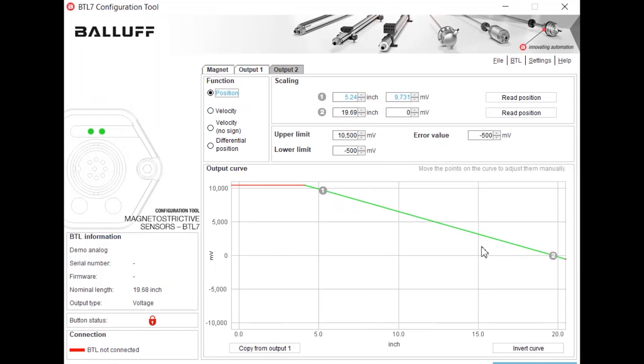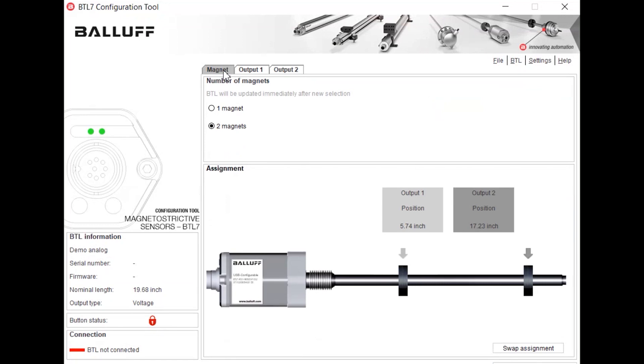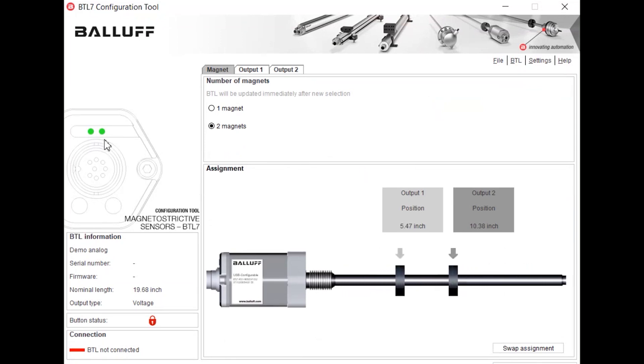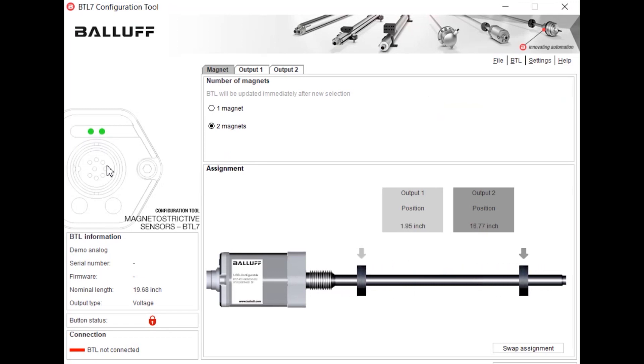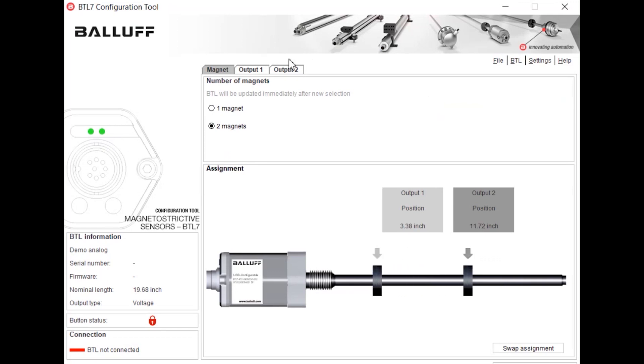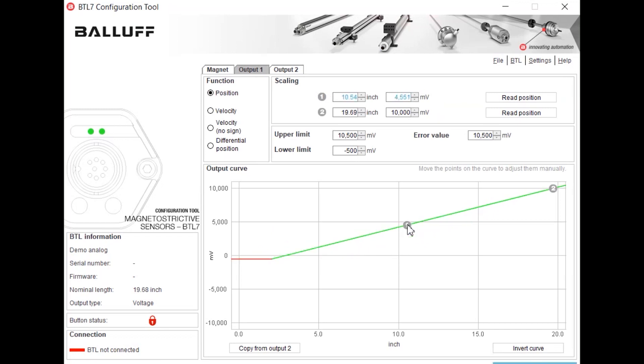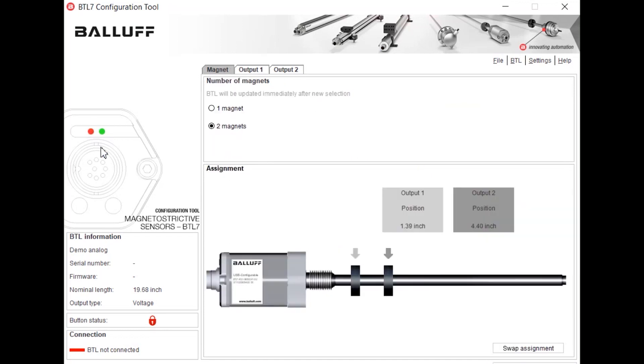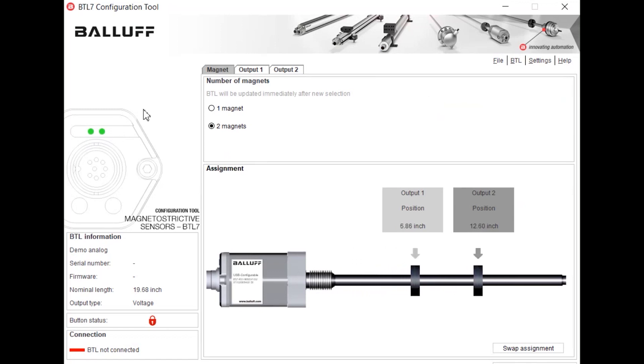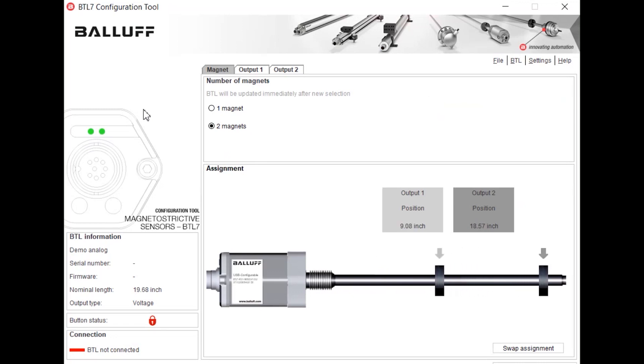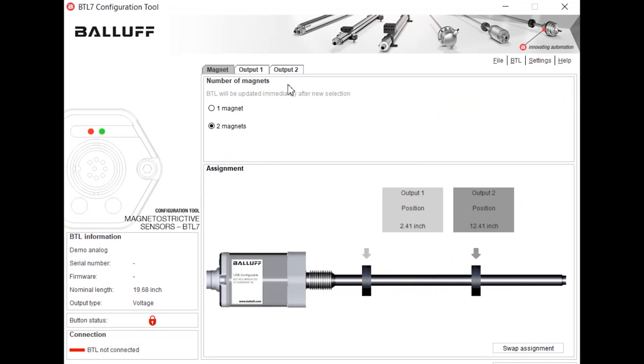And as you can see here we're getting the indicators for the magnets; they're both green that means they're both in the correct position and they're both being read. But if we go ahead and change here, as you can see we're now getting a red light showing that it's not in the taught range or the scaled range for the measurement.